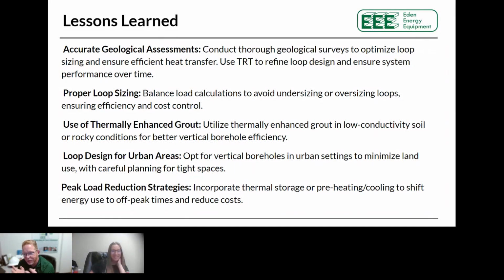So as we look at ground source and lessons learned, number one is just do the proper assessments. If you're doing a ground loop, don't rely on rules of thumb. Take advantage of TRT, figure out how many watts per degree you can get out of that loop, and make sure you're sizing things properly.